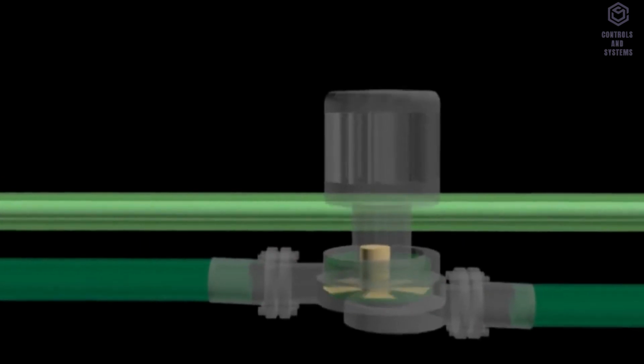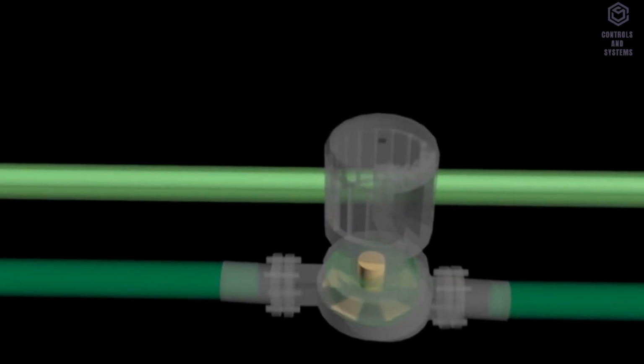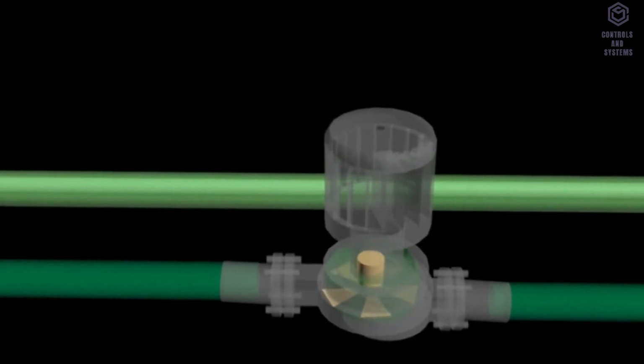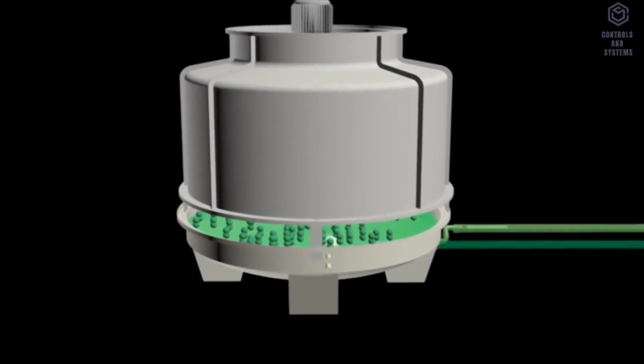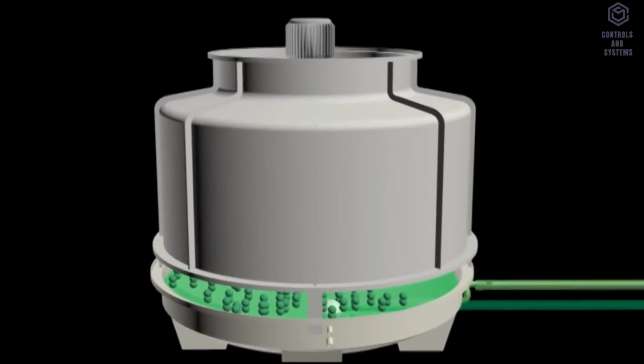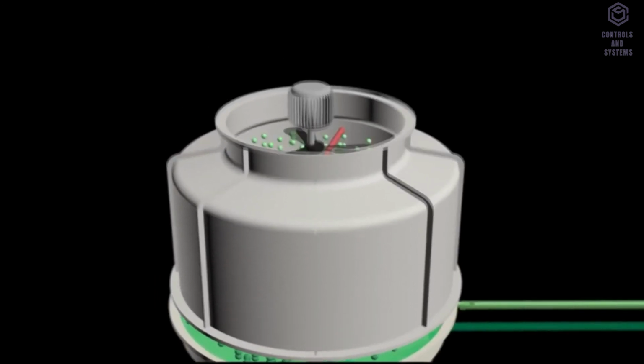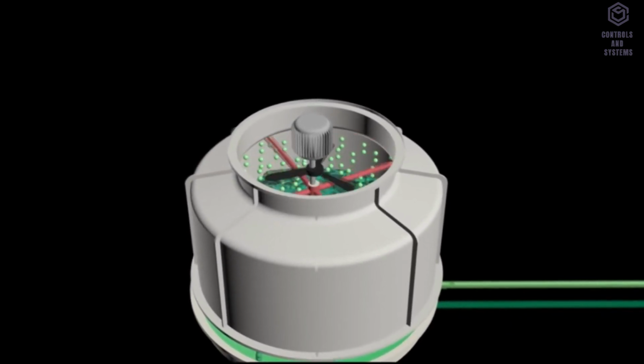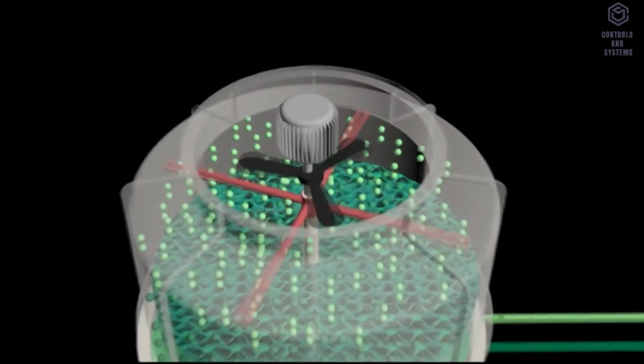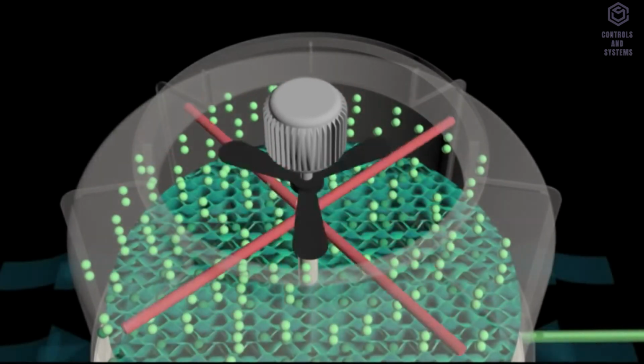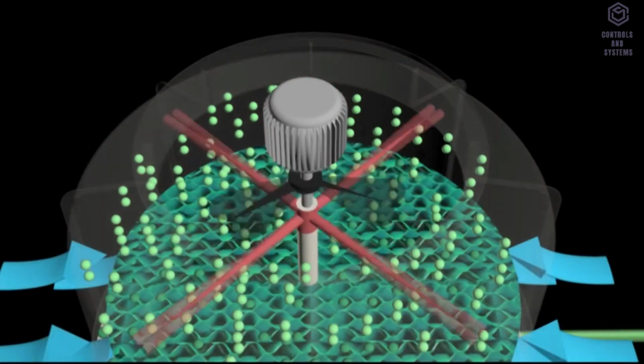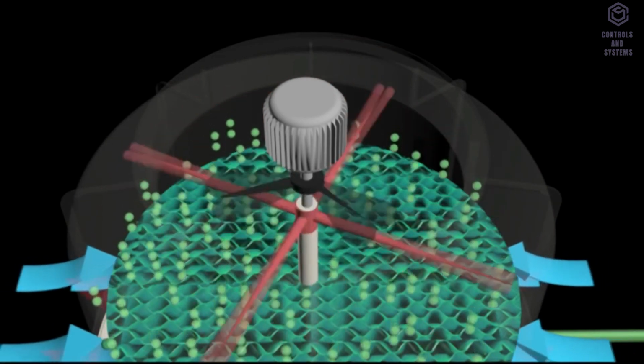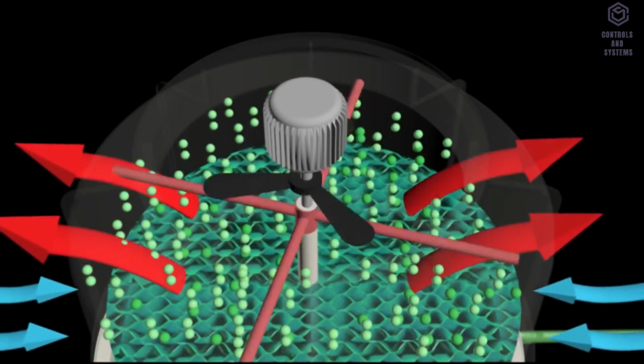Heated from the condenser in the chiller, condenser water flows to the cooling tower with the help of the centrifugal pumps. This water is called condenser water return. The condenser water will pass through the rotating sprinkler blade on the cooling tower. This rotating blade uses pressure generated by the condenser water itself. Water goes down through the fins and the speed of the water going down is reduced.